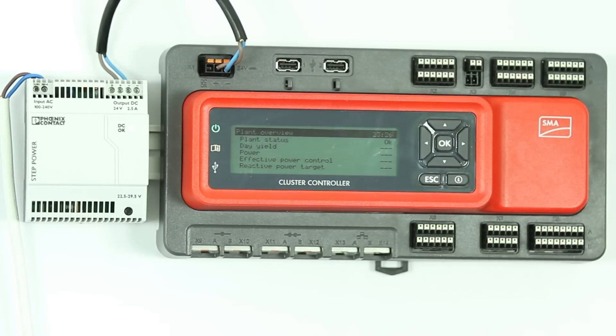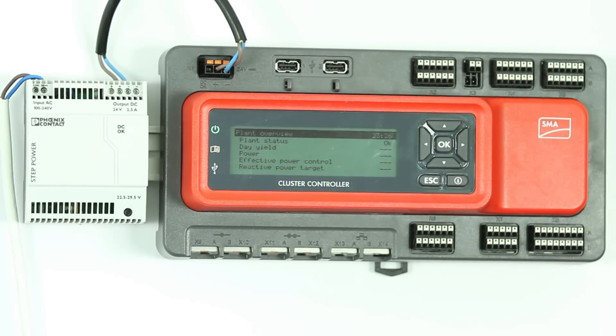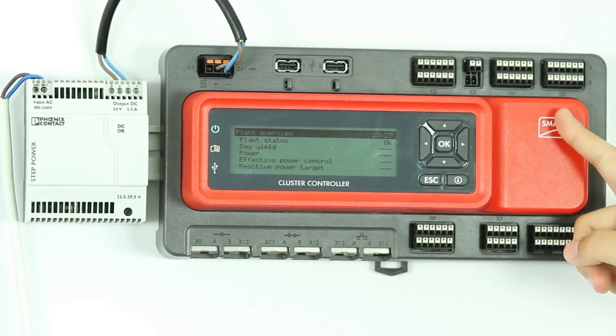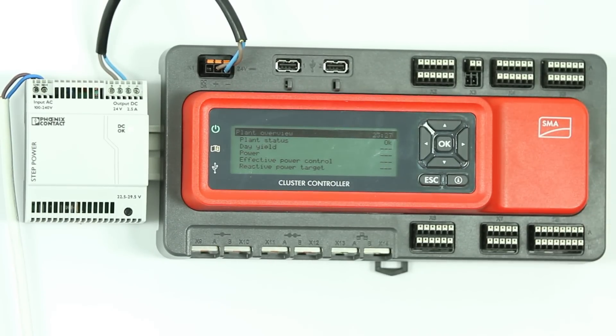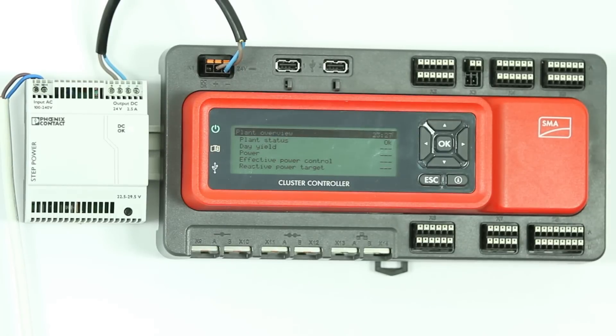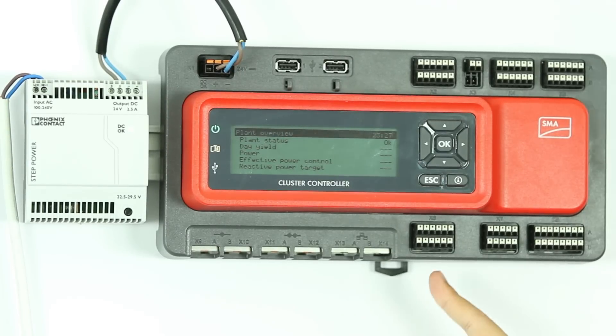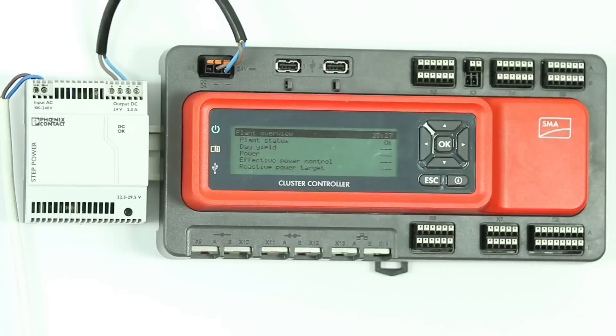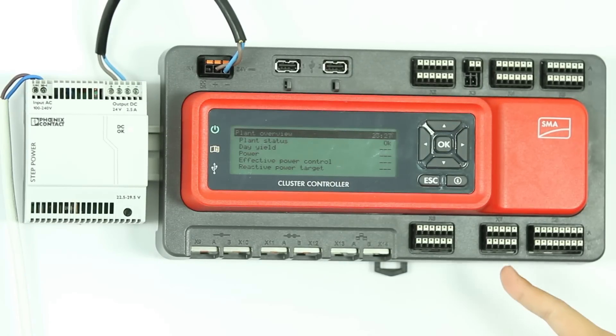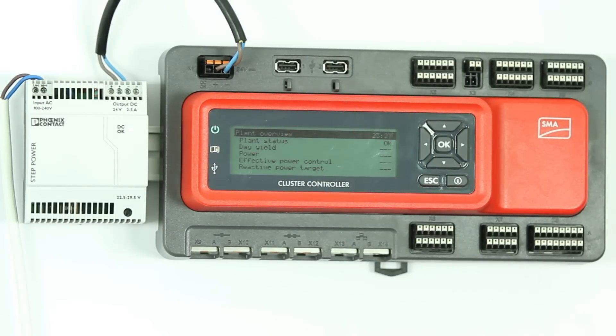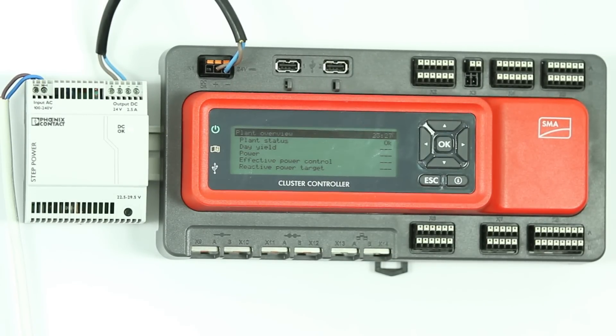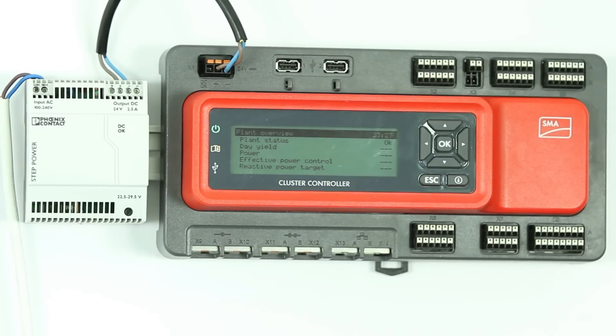X4 allows for four digital inputs for active power limitations. X5 allows for four digital inputs for reactive power limitations. X6 allows for two analog outputs for the feedback of current active and reactive power limitations. X7 allows for two PT ports for analog signals from ambient and module temperature sensors.